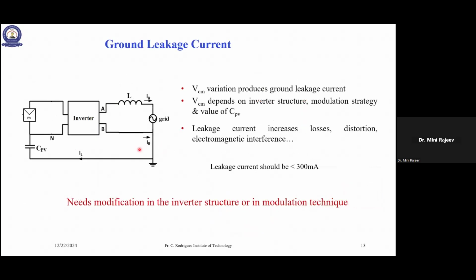So this VCM means common mode voltage. Common mode voltage variation produces ground leakage current. And again, the magnitude of that depends on the structure of the inverter, the modulation strategy, as I said, unipolar, bipolar, and also the value of CPV. The value of CPV, we have already seen how it gets affected. And this leakage current will increase the losses. As it is a high frequency current, it will increase the distortion. It will interfere with the radio frequency signals. So overall, this leakage current needs to be eliminated.